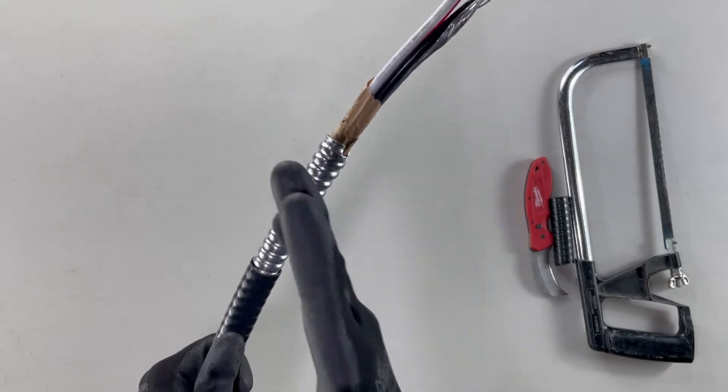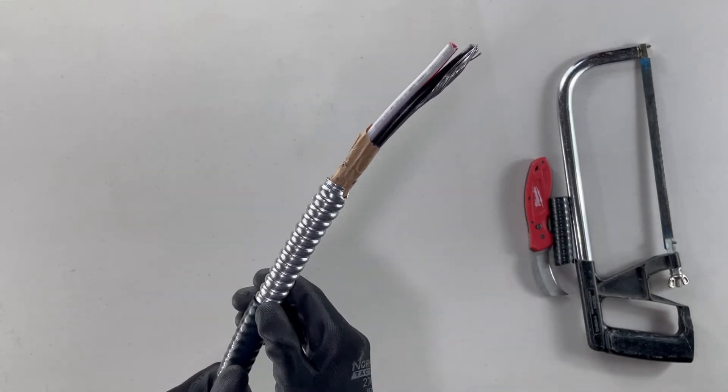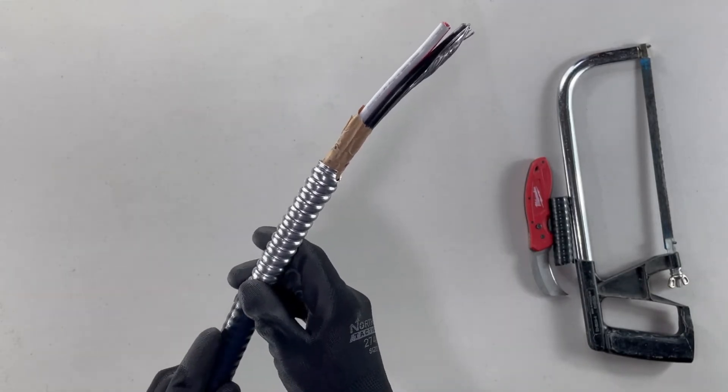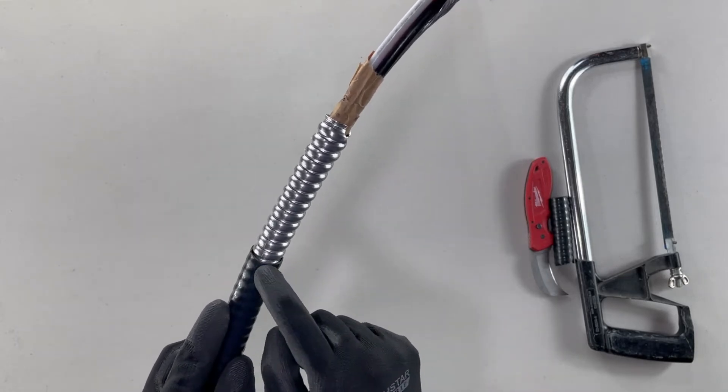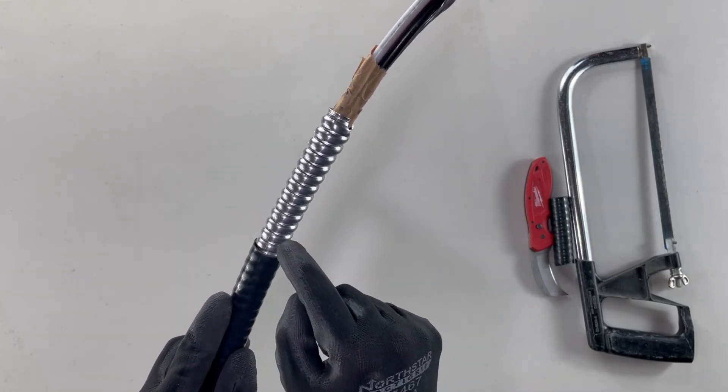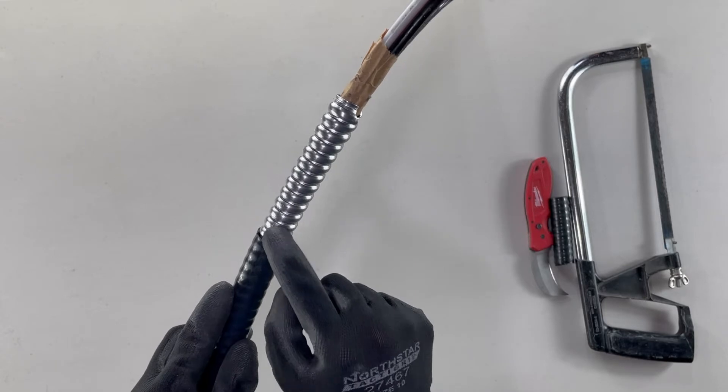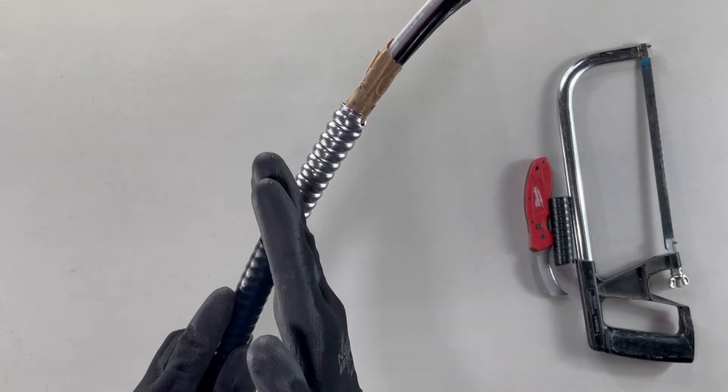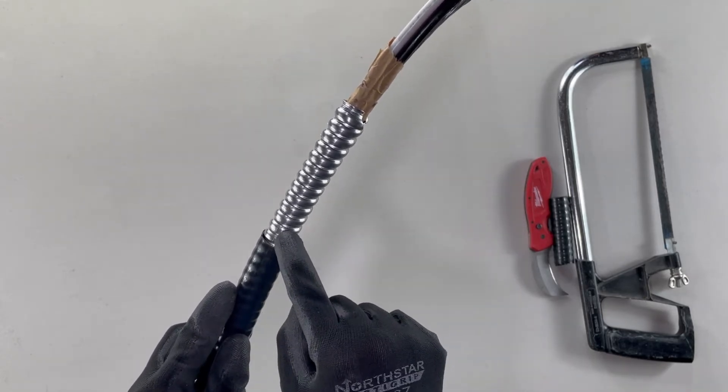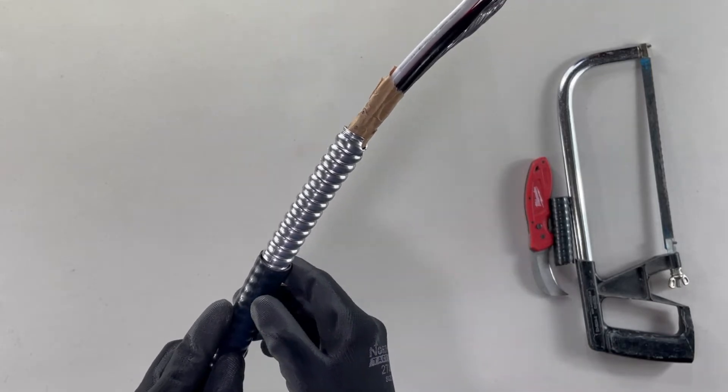Next, you're going to want to cut on an angle with your saw, similar to the way that you would strip BX. And you're going to be very careful not to go too far down through this casing. You really just want to score it, almost just nick it a little bit. Otherwise, you risk damaging the conductors underneath.